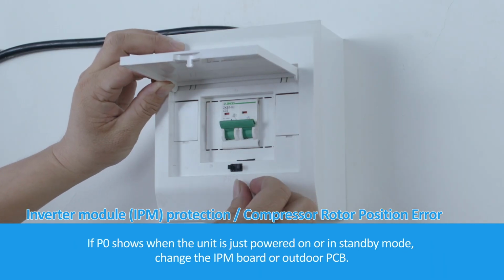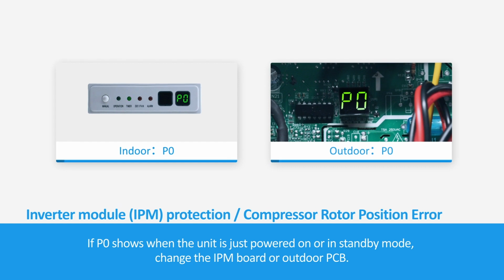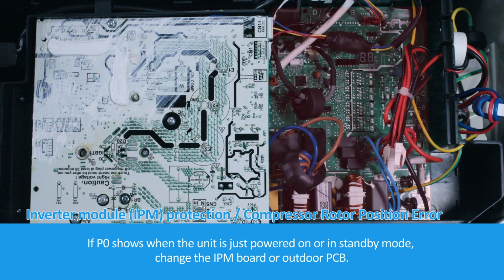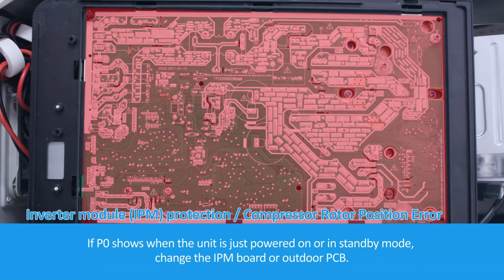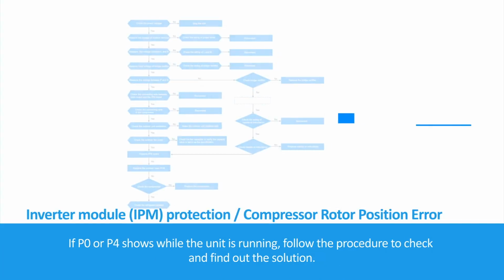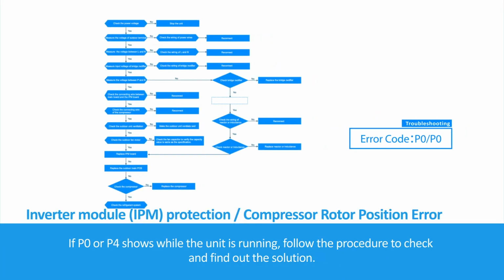If P0 shows when the unit is just powered on or in standby mode, change the IPM board or outdoor PCB. If P0 or P4 shows while the unit is running, follow the procedure to check and find out the solution.